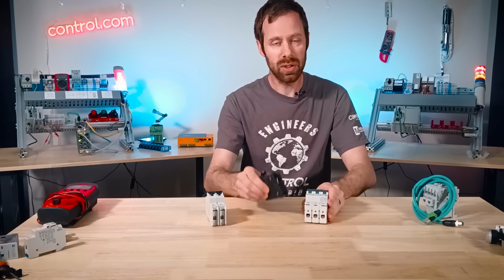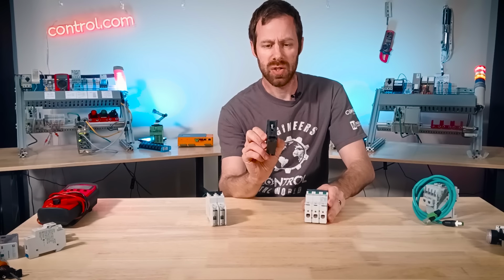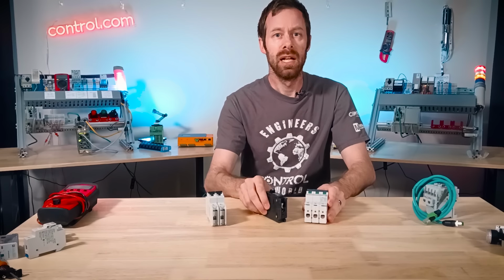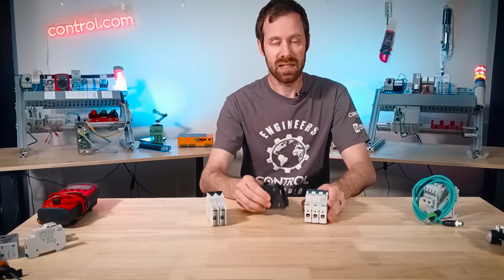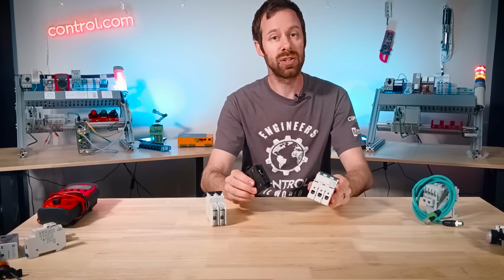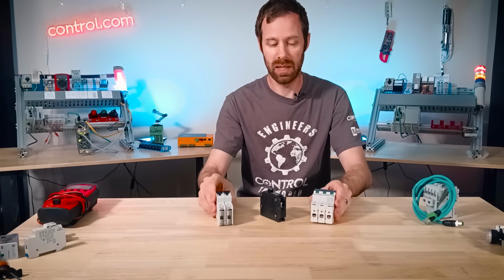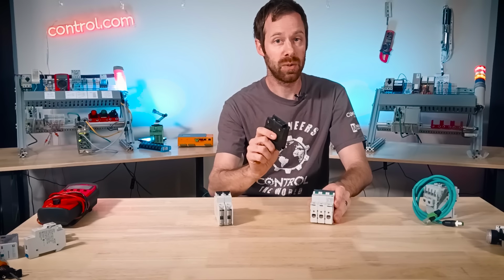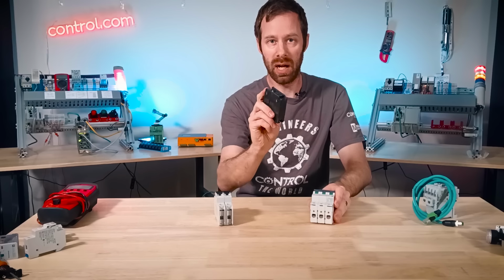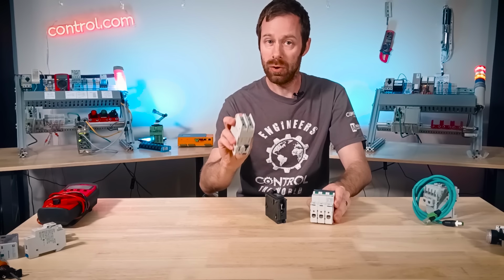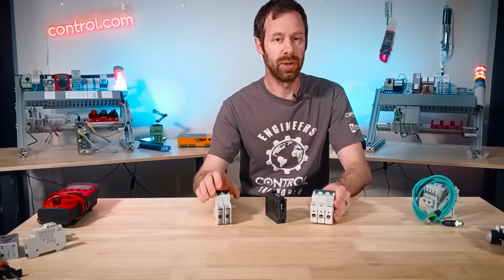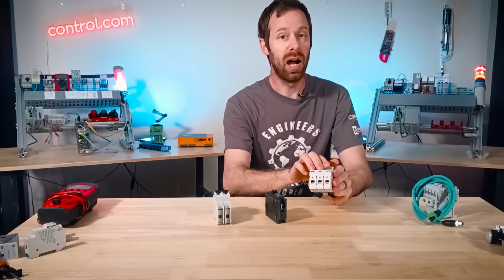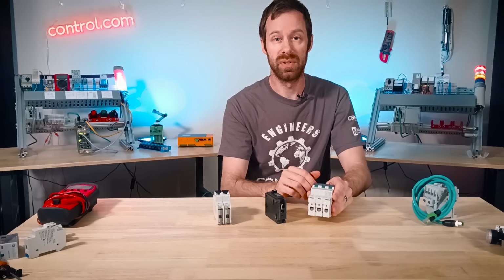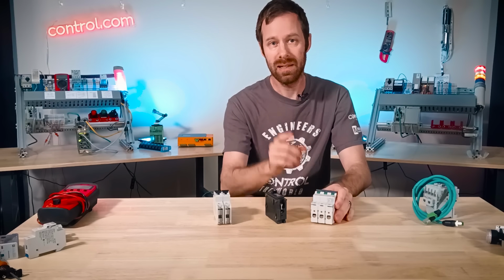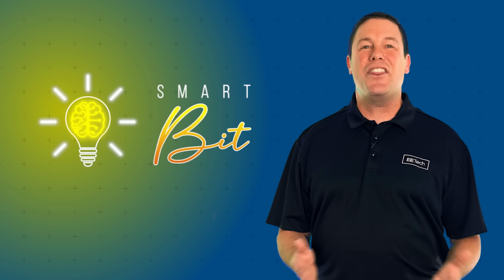So while it might look a little different, one circuit switched on and off to turn off a 2-wire device seems a bit different, but they're actually exactly the same kind of system. It's just a matter of how many hot wires we have: 1 hot wire for your lights, 2 hot wires for your dryer or stove, but 3 hot wires to run industrial loads like motors. Andy, back to you. Thank you, David.